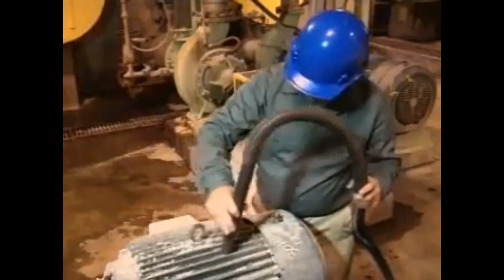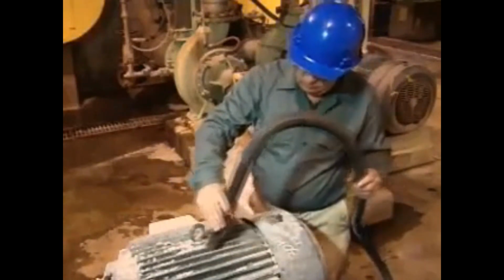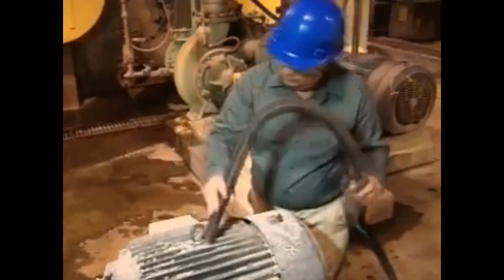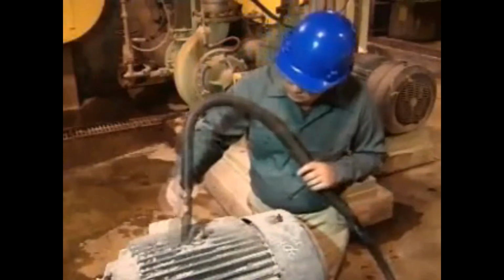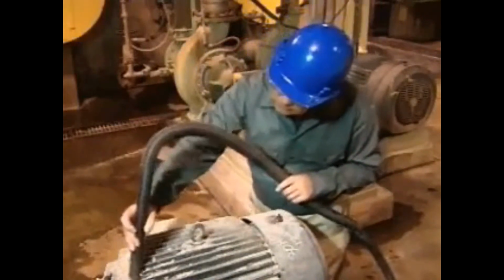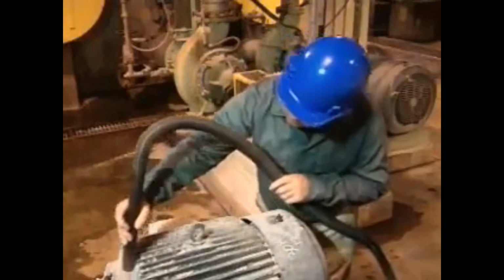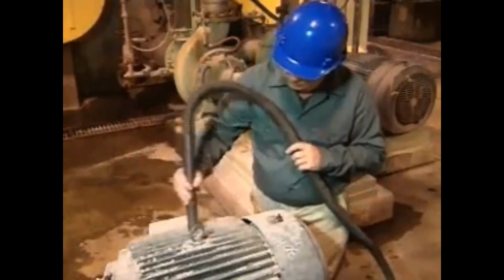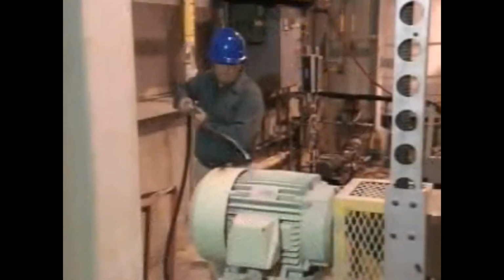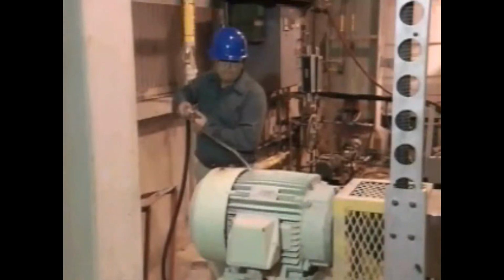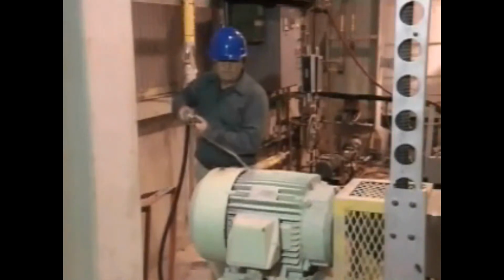By taking these routine maintenance actions, you'll ensure continued efficient operation of the equipment. If the motor is not operating, use a vacuum cleaner to clean the exterior of the motor to remove dirt and dust from the vents. If the motor is operating and your facility allows the use of low-pressure air in cleaning, direct the airflow through the motor to remove dust and dirt from the vents. This procedure will keep you away from moving parts during operation.